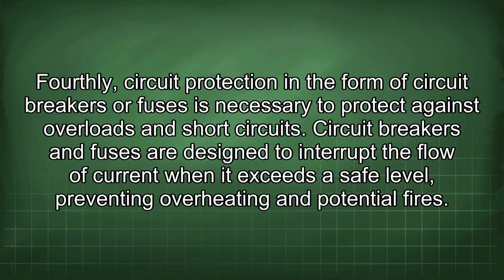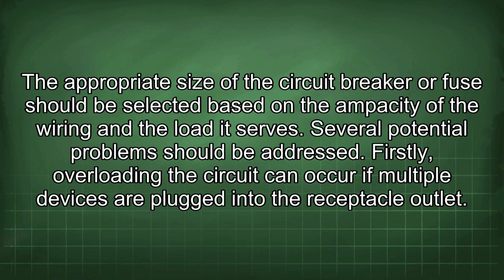Wires should be protected from physical damage, such as abrasion, cuts, or crushing, which can compromise the insulation and create a hazard. Fourthly, circuit protection in the form of circuit breakers or fuses is necessary to protect against overloads and short circuits. Circuit breakers and fuses are designed to interrupt the flow of current when it exceeds a safe level, preventing overheating and potential fires. The appropriate size of the circuit breaker or fuse should be selected based on the ampacity of the wiring and the load it serves. Several potential problems should be addressed.